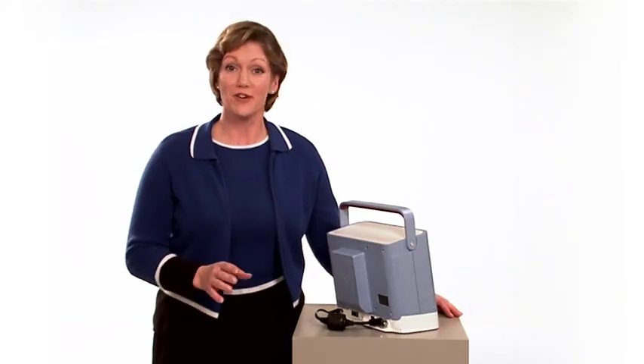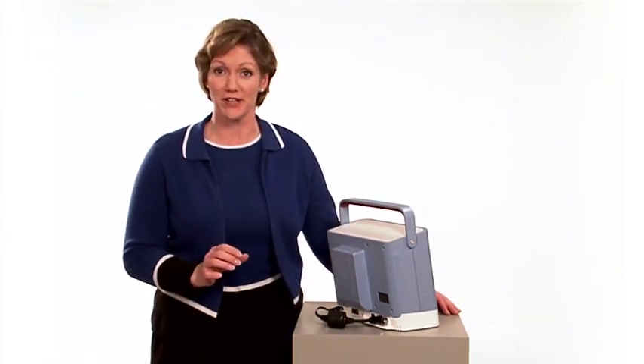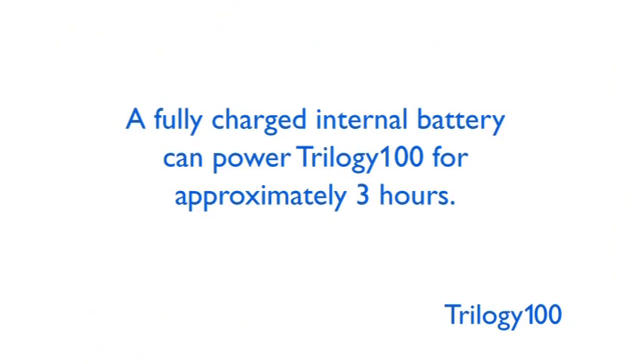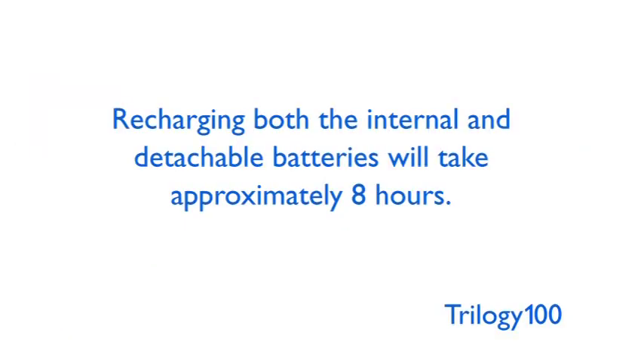Trilogy 100 also has an internal battery, which can be used as a backup power source for shorter periods, so the ventilator stays on while you switch between external power sources or transport a patient. Under typical conditions, the internal battery can power Trilogy 100 for approximately 3 hours. When Trilogy 100 is connected to AC power, it will automatically recharge both the internal battery and the detachable battery pack. A completely discharged internal and detachable battery will take about 8 hours to recharge.